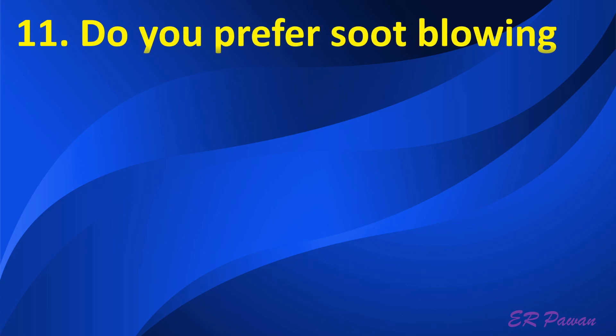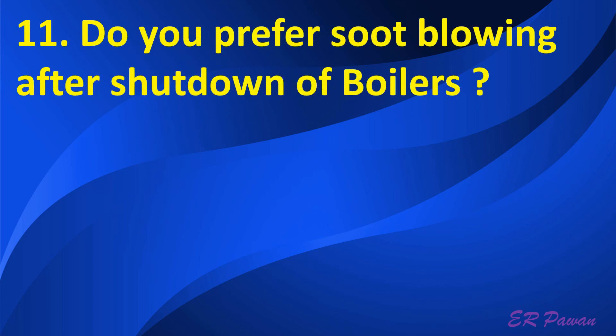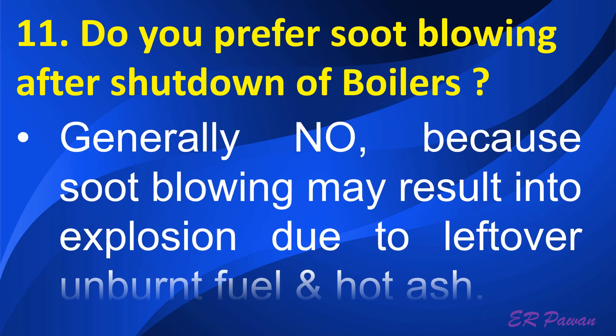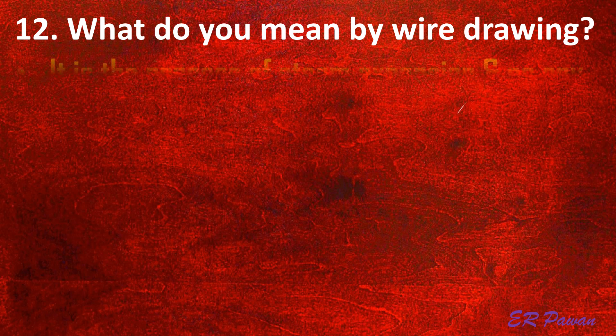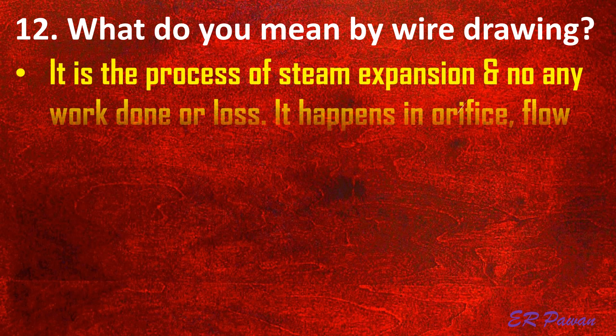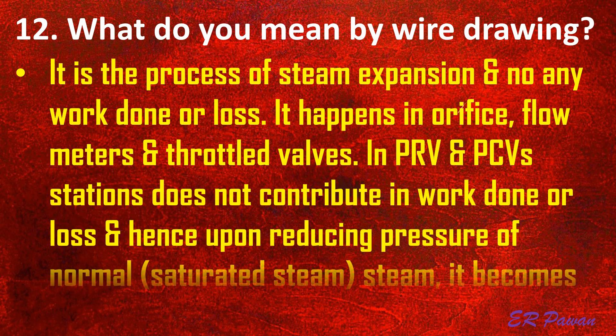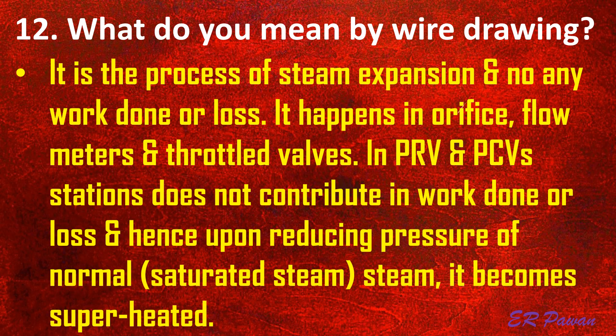Question 11: Do you prefer soot blowing after shutdown of boilers? Generally no, because soot blowing may result in explosion due to leftover unburnt fuel and hot ash. Question 12: What do you mean by wire drawing in boilers? It is the process of steam expansion with no work done or loss. It happens in orifices, flow meters, and throttled valves. In pressure reducing valves and pressure control valve stations, it does not contribute to work done, and hence, upon reducing pressure of normal saturated steam, it becomes superheated.